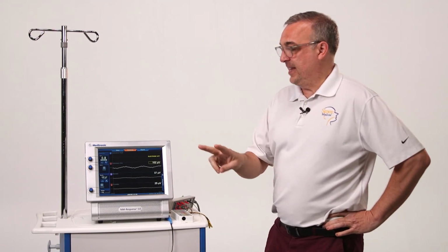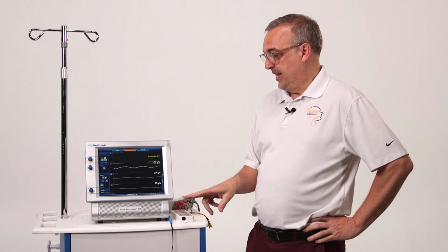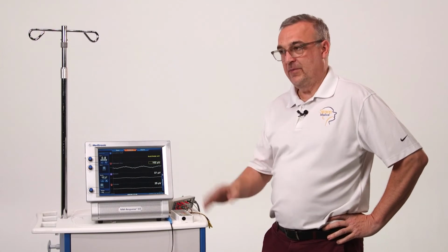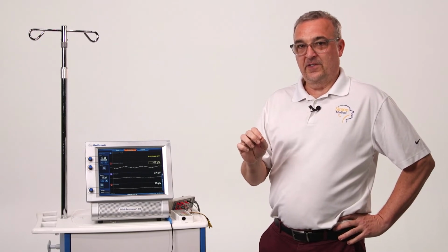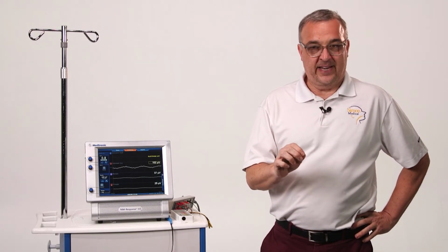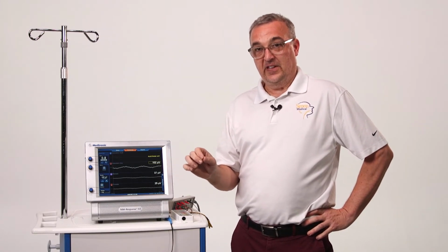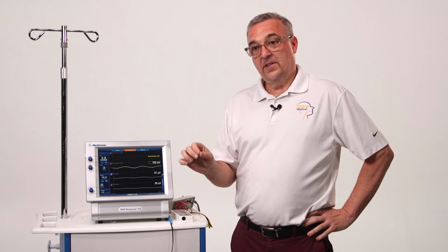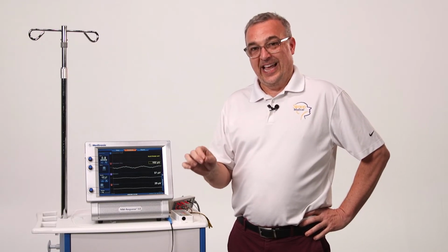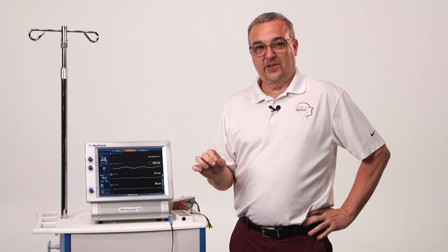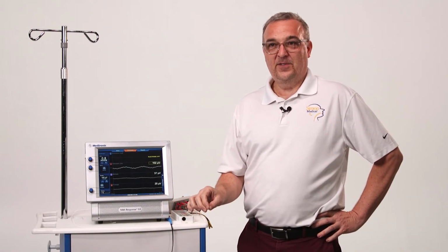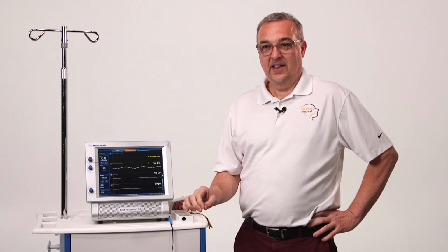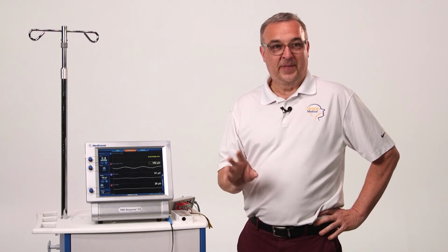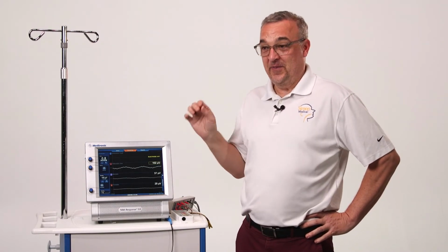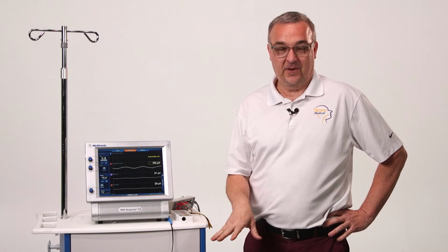The other two things that frequently happen are you're gonna get a lot of just EMG response in all the channels. That is one of two things. That's either somebody's moved a cautery box or something with electromagnetic interference into the field or near the NIM, or the patient is actually getting light in anesthesia. And that's not always a popular topic with anesthesia to bring up, because you say, are they getting light? And they say, no, but a minute later you see them pumping up the gas a little bit because they are getting light. So the NIM is very sensitive if the patient is getting light in anesthesia.